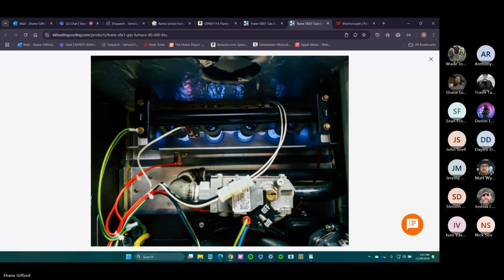And believe it or not, yes, the Denny's in Coeur d'Alene, that's their makeup air unit, is like a big barbecue grill in their ductwork. It just turns on. There's a flow switch, a sail switch, to make sure the blower is going. But that's about it. You've got a sail switch, a little board, and a gas valve.